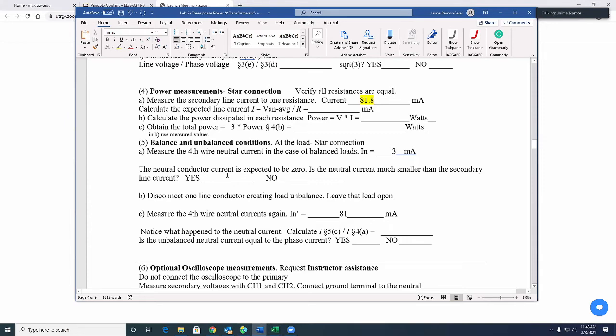Okay, so that's the balanced condition. Now we go to the unbalanced condition, and for that we disconnect. And after disconnecting, we measure the neutral current again, and now it's 81 milliamps. So look, the current went from 3 milliamps in the balanced condition up to 81 milliamps in the unbalanced condition. And this 81 milliamps is just equal to the phase current. So how can that be? Well, the reason is this. Look.